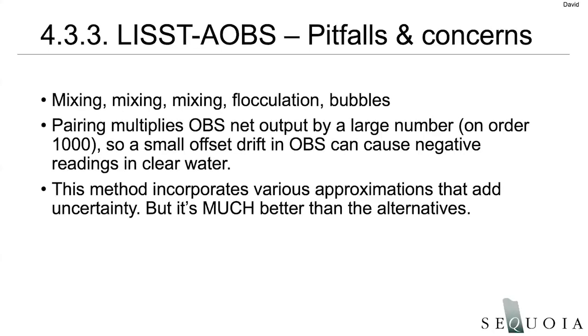Once we've sent a few of these out into the field and gotten a little bit of feedback from customers, the particular OBS that we're pairing is not highly sensitive. You can choose different OBSs that have different degrees of sensitivity. The one that we use, the Turbidity Plus, at least on its standard sensitivity range, is not a super sensitive OBS because we wanted to make sure that it would never saturate within the range that's measured by the ABS. What that all means is that the offset drift in the OBS, once you multiply it by the pairing factor, can turn into something on the order of a few milligrams per liter. And so it is possible that the offset drift can give you negative readings of a few milligrams per liter. And, nobody likes to see negative turbidities.